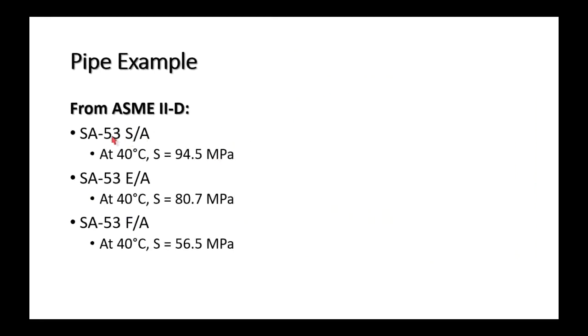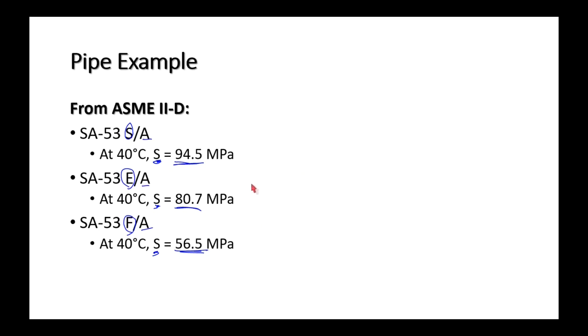To summarize — comparing seamless, ERW, and Type F furnace butt weld, all Grade A, SA-53 pipe at 40°C: the allowable working stress for seamless is 94.5 MPa, for ERW it's 80.7 MPa, and for furnace butt weld it's 56.5 MPa. To find the joint efficiency: 80.7 ÷ 94.5, and 56.5 ÷ 94.5.